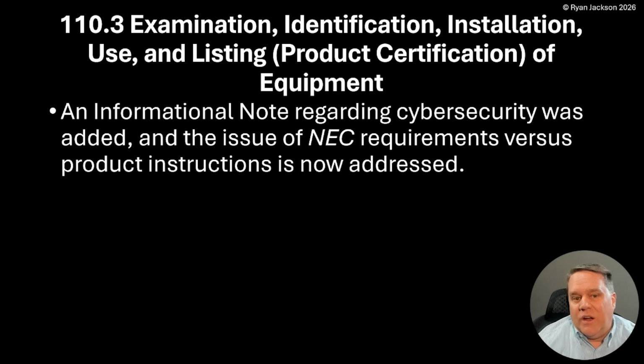A lot of testing laboratories are getting away from the word 'listed,' because listed means your name is on a list. Back in the day, there was a literal list - UL and these companies would put your name on a list of equipment suitable for specific applications. I don't know that there's an actual literal list anymore, other than an online database. So is listing really about writing your name on a list? No, what they're doing is certifying the product - putting their stamp of approval, whether it's UL or Intertek or whomever, saying this product is built in accordance with recognized product safety standards, and we're certifying that it does.